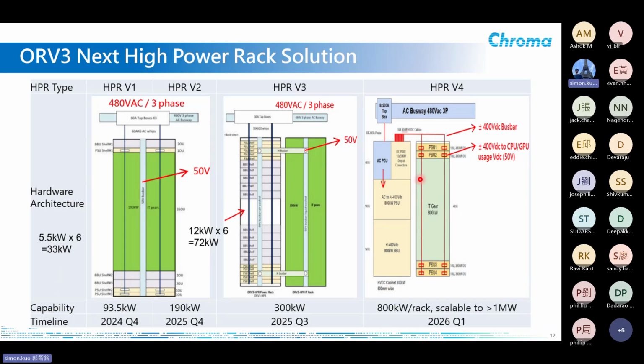The next generation, which we'll see in 2026, is the HVDC. It's still a sidecar idea, but they will transmit the voltage as high VDC. The AC goes from the top to the AC-to-DC rack, then we have the output of 400 volts or even 800 volts, with a PDU to cover it. We have 800 volts shifted down to 50 volts converted, and then it goes into the IT gears. So this is what we'll see in 2026.